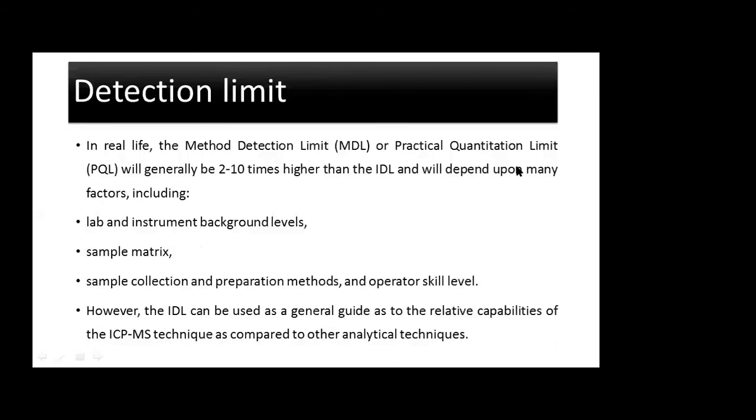In real life, the method detection limit, or MDL, which is also called the practical quantitation limit, or PQL, will generally be 2 to 10 times higher than IDL. So instrumental detection limit is different from the practical one.